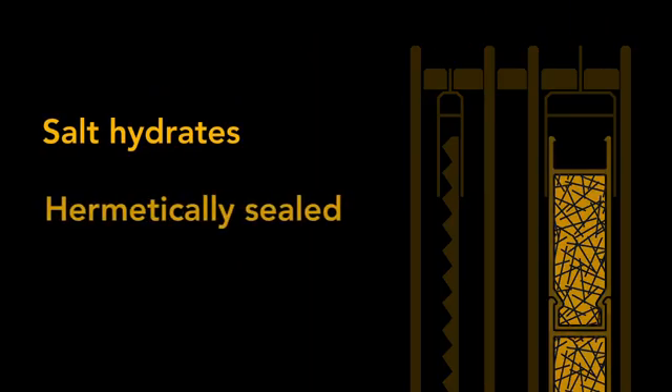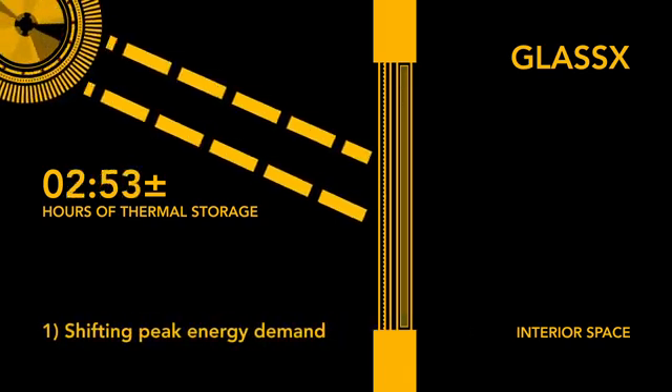The PCM core of GLASSX is comprised of salt hydrates, hermetically sealed in clear polycarbonate. It has a latent thermal storage of up to 375 BTUs per square foot, which means, on average, 6 to 10 hours before heat is transferred. This solar heat storage has two effects: one, shifting peak energy demand later into the night when temperatures typically fall off; and two, reducing average interior room temperatures by 3 to 5 degrees Celsius.